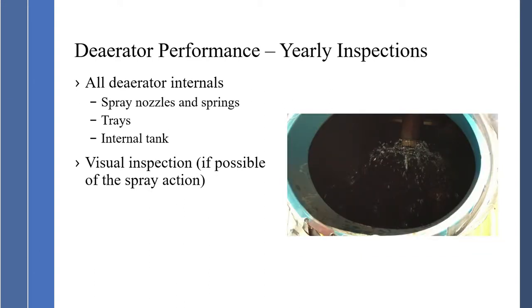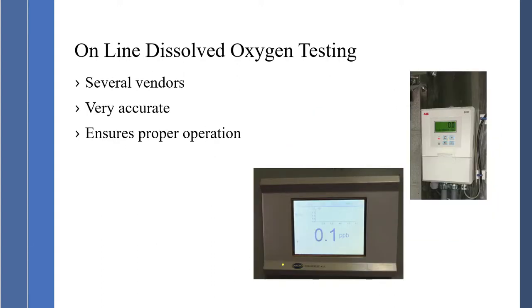Another method is online dissolved oxygen testing, which is a great device to have on deaerators. There are several vendors and they are very accurate, ensuring proper operation of the deaerator. These give us a real-time measurement of dissolved oxygen — this one is running at 0.1 parts per billion, which is outstanding, and this one is going through calibration measuring zero.